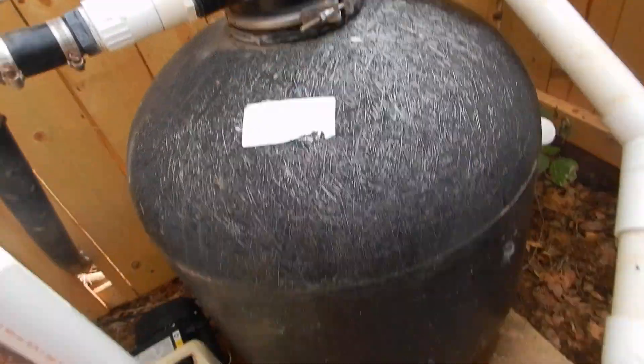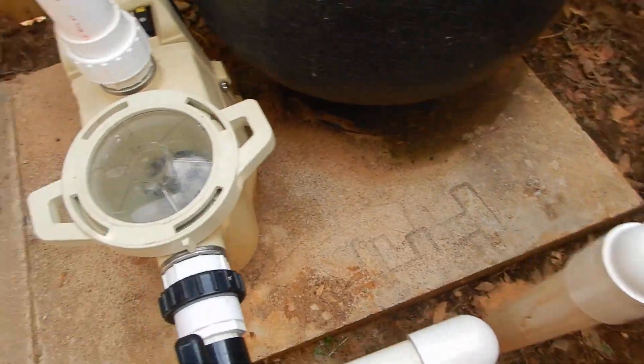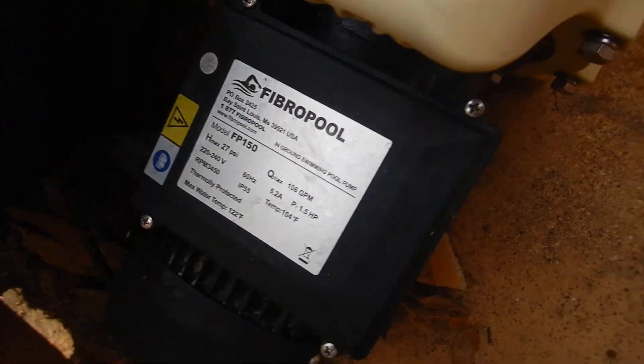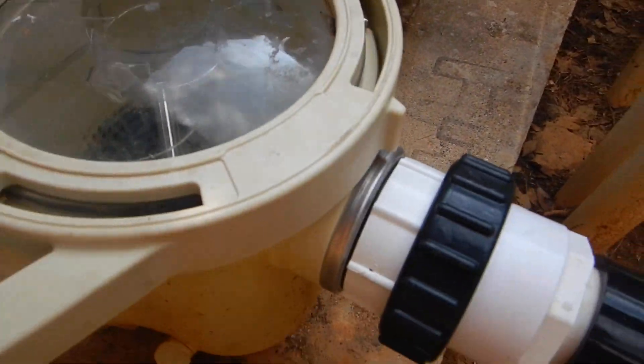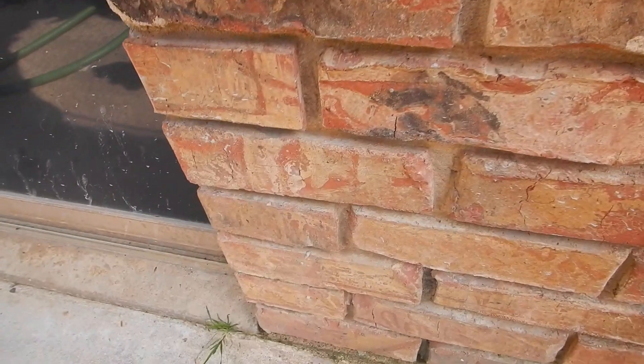So here we are at 30 psi. Our valves are not labeled. It looks like we've got a newer pump motor, but I can't find any data on the pump itself. The pump looks older. Our water supply does not have a vacuum breaker on it.